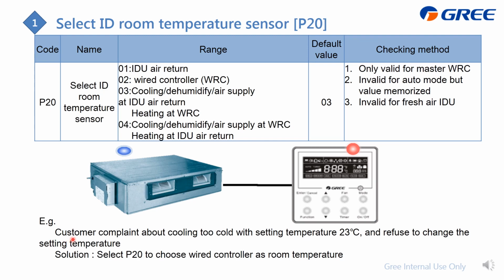that the customer complained that the cooling is too cold with the setting temperature at 23 degrees, and refused to change the setting temperature. This may be due to the temperature sensor, whose default setting in cooling is at the air return. You can change it to here, which is closer to the customer. Then this may change the room temperature. The solution is that the service person selects P20 and chooses the wired controller as the room temperature sensor.